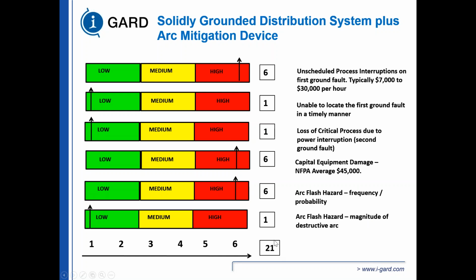So we went from 26 to 21 in the risk assessment meter, but we've made it safer by implementing arc flash relays. So we lowered the magnitude or severity of an arc flash, but we haven't lowered the frequency of an arc flash. And many of you who were at the presentation from 2 weeks ago was discussing why high resistance grounding is an arc flash mitigation technique. Again, we can circulate that link again, and you're free to look at it and determine why NFPA 70E and Z462 have established high resistance grounding as an arc flash mitigation technique, because it lowers the frequency, not the magnitude.